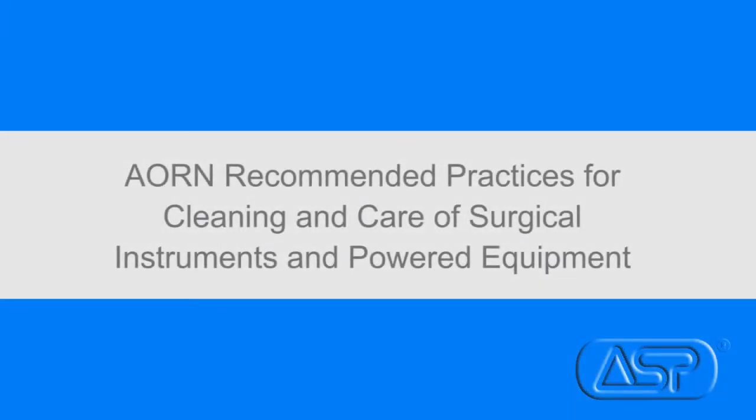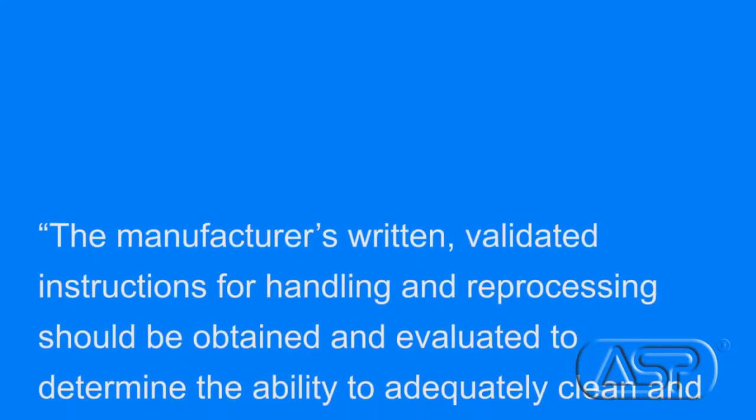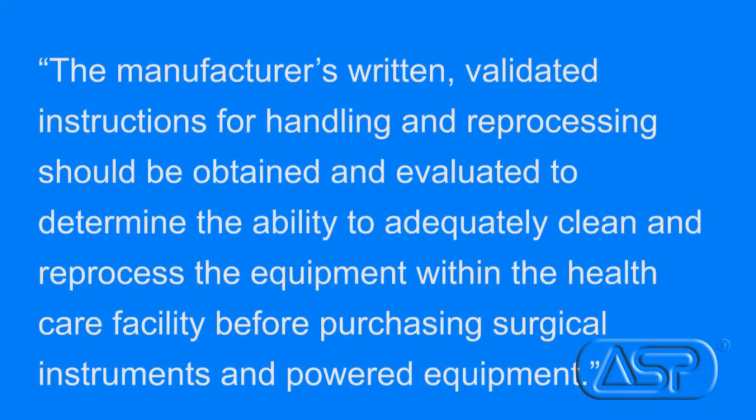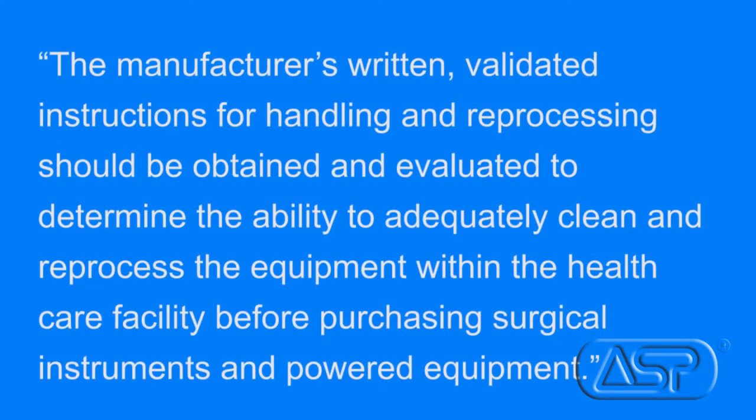AORN also supports AAMI ST79 and states in their recommended practices for cleaning and care of surgical instruments and powered equipment that the manufacturer's IFU should be obtained and evaluated to determine the ability to adequately clean and reprocess the equipment within the healthcare facility before purchasing surgical instruments and powered equipment. Because the Joint Commission and other agencies want to make sure you are following the most updated standards and instructions, it has become the facility's responsibility to comply with the latest IFUs.